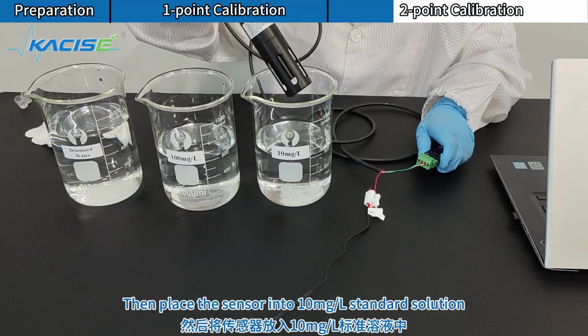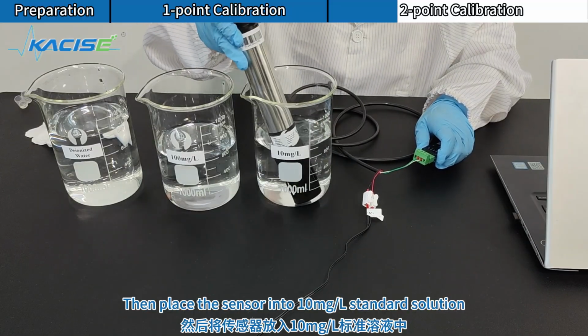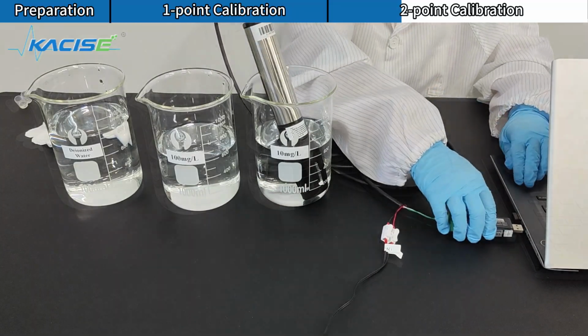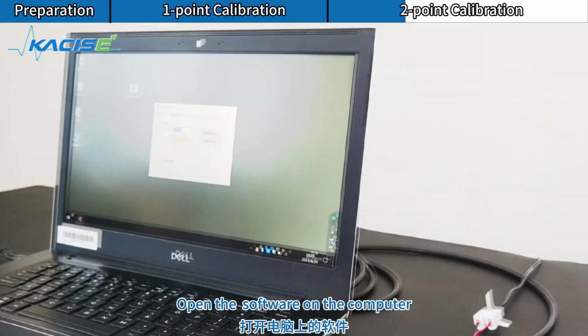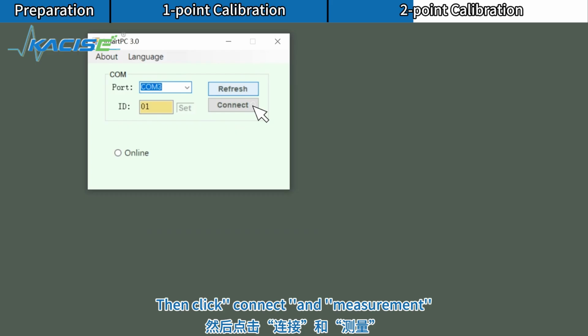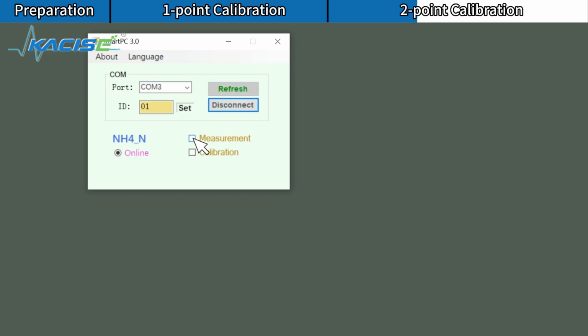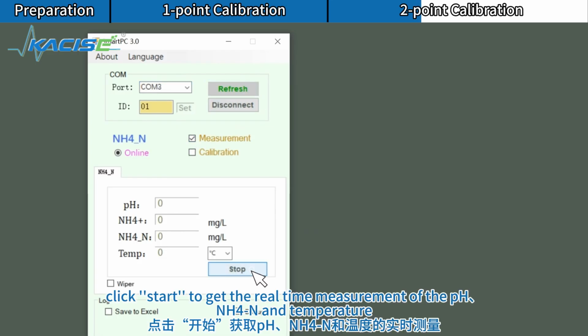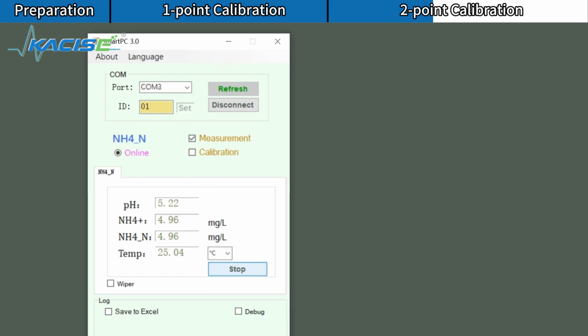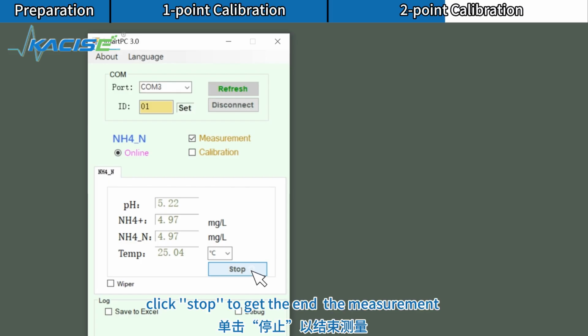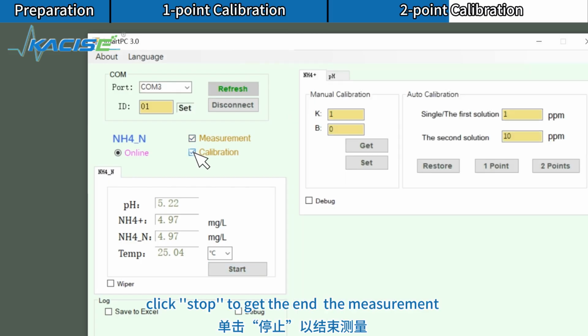Then place the sensor into the 10 mg/L standard solution. Open the software on the computer. Then click Connect and Measurement. Click Start to get the real-time measurement of the pH, NH₄-N, and temperature. Click Stop to end the measurement.